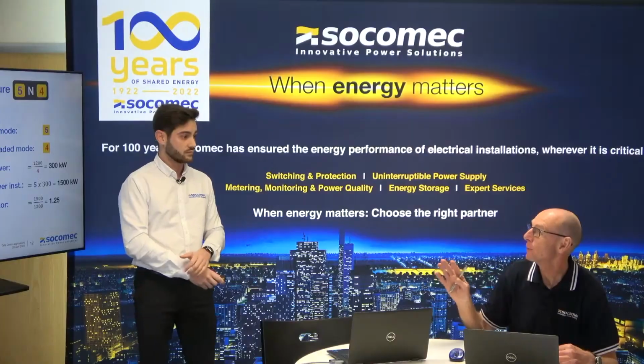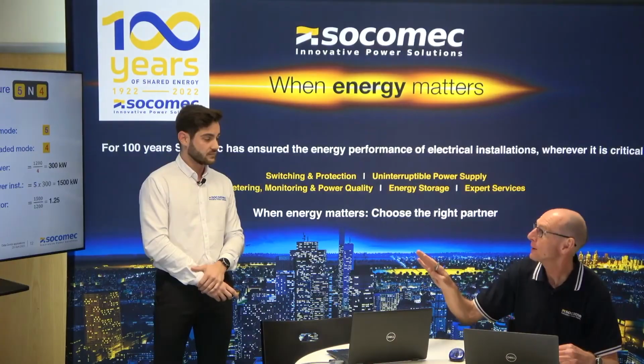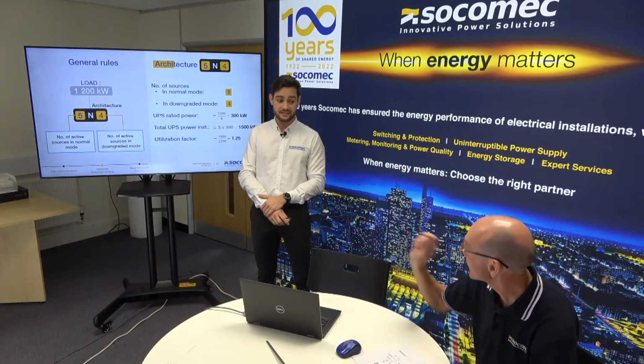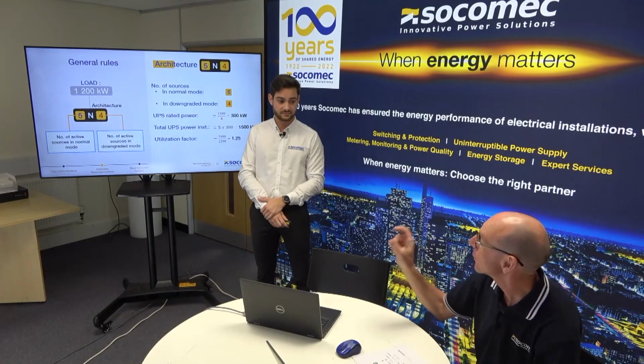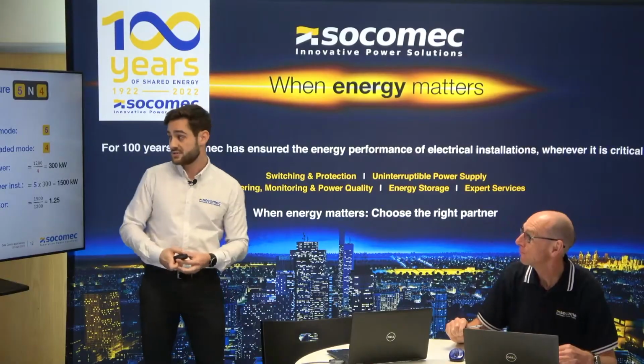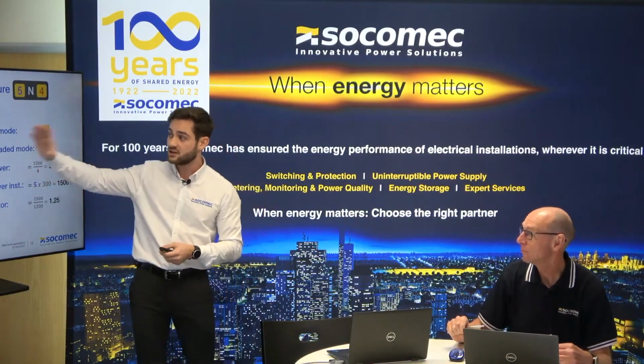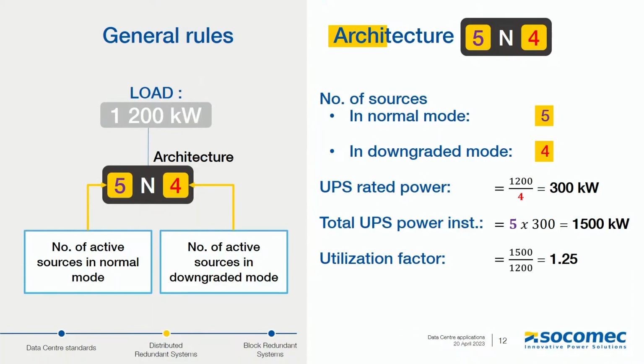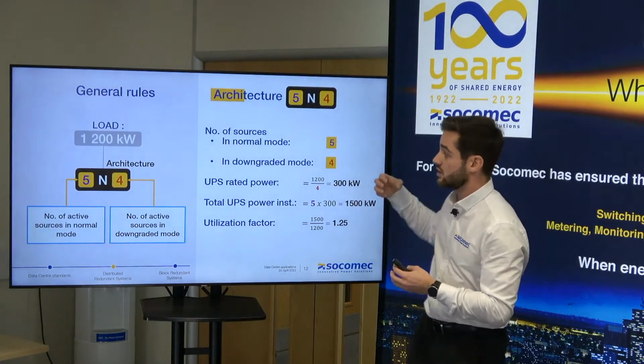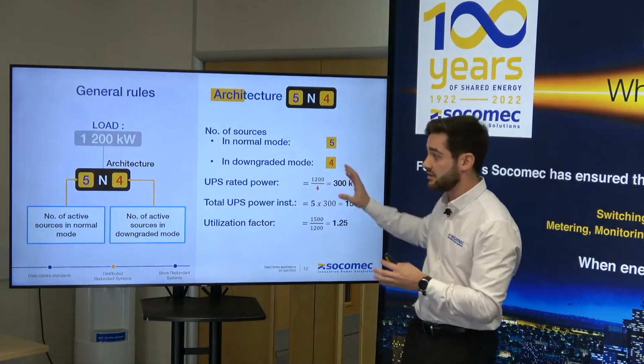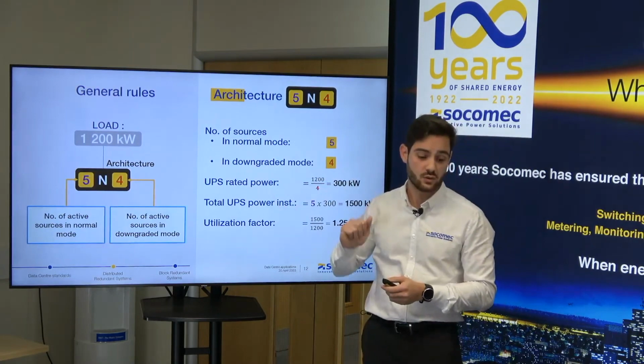Sorry, just to interrupt, but in all cases, the load architecture is still 1200. That's the key point here. You're sizing it for the load. It is 100%. So we are still looking at a 1200 kilowatts load, with a system that has the same reliability as a 2N system. So even if we've got a failure on one system, we are still able to cover this 1200 kilowatts load with the other systems. Yeah.